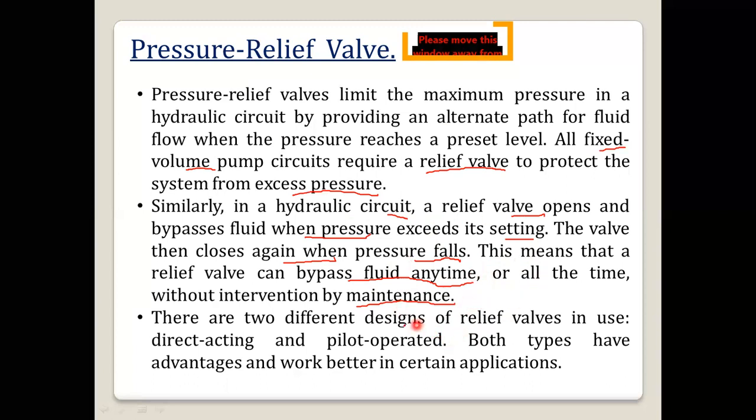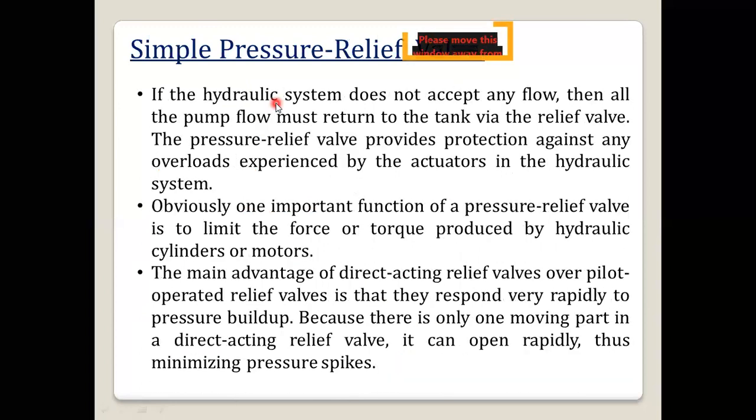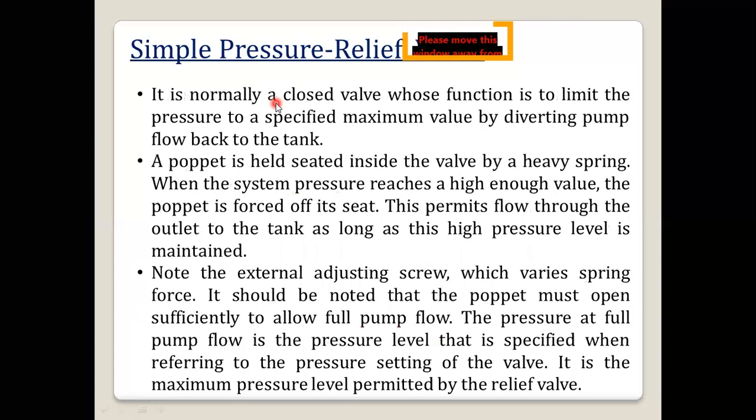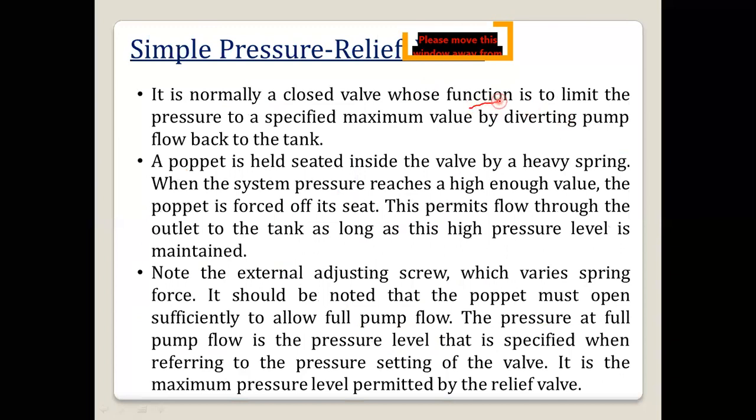Okay, so basically there are two designs of pressure relief valves. One is the direct acting, and the second one is the pilot operated. Both types have their advantages and their applications. Okay, so the pressure relief valve is a closed valve, and its function is to limit the pressure to a specified maximum value.